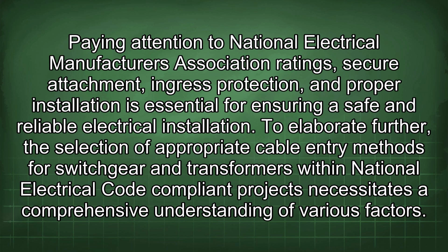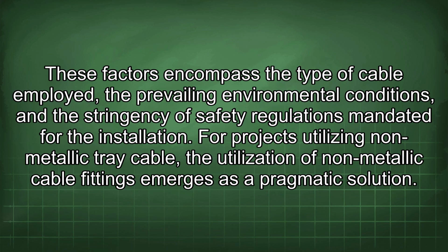To elaborate further, the selection of appropriate cable entry methods for switchgear and transformers within National Electrical Code compliant projects necessitates a comprehensive understanding of various factors. These factors encompass the type of cable employed, the prevailing environmental conditions, and the stringency of safety regulations mandated for the installation. For projects utilizing non-metallic tray cable, the utilization of non-metallic cable fittings emerges as a pragmatic solution.